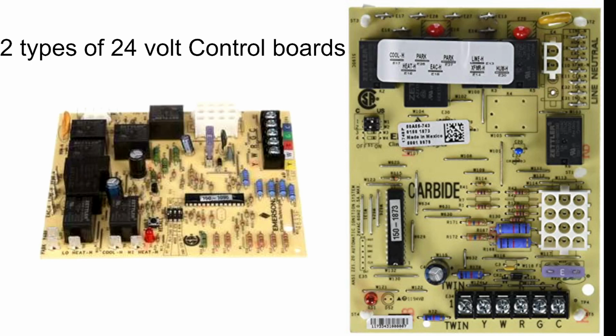Y on the system is your cool. That's the cool side of your system. W stands for heat. R is power. That's the feeding power that comes into it. G is your fan control, which is your blower on the indoor unit. And C is common. So if you want to measure to make sure that your 24-volt transformer is working, all you have to do is take a multimeter and go from power, which is R, and C, which is common, and you go across it.